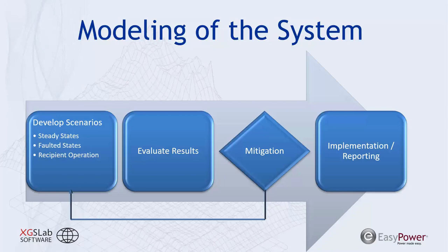And if you need some sort of mitigation for this or you're exceeding your limits, you typically have to rerun all of your analysis, because any mitigation effort that you incorporate may have effects on the steady state results, on the faulted results, and on how the recipient's different operational configurations will be affected. So it's a very iterative process, and typically any change that you make in your model is going to have a cascading effect for the rest of the system.